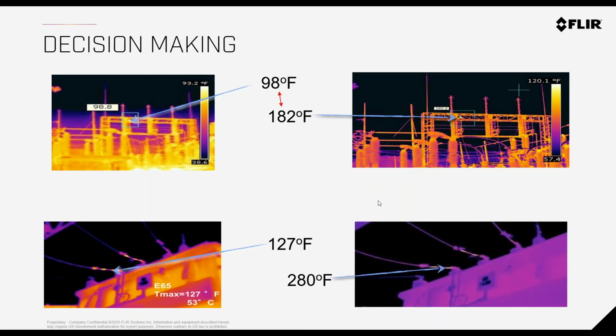And then we look at this one over here where it was 127 degrees. Now we put a more powerful camera on it, and we see that it's actually 280 degrees Fahrenheit. So if you took this image and said, hey, 98 degrees, that's pretty normal, this thing should operate at 98 degrees, but you didn't know that in reality it was 182 degrees, your decision making is going to be vastly different. So it's important that you have the right camera for the right application.